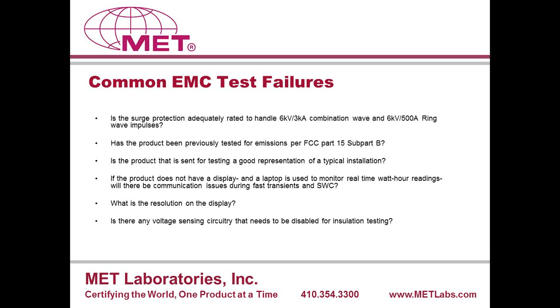Sometimes if you have too much resolution, too many digits after the decimal point, what we see is that in some of the tests like fast transients and radiated immunity, the watt-hour accumulation is changing or increasing. If you have too many digits after that display, we see that happening quite a lot. So when you send your product for testing, you want to make sure that you have enough resolution, but you do not want too much resolution that would cause some issues on tests.